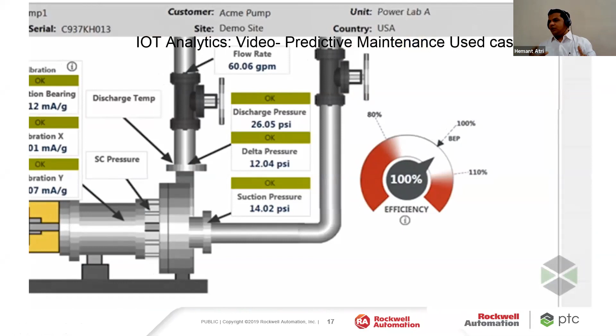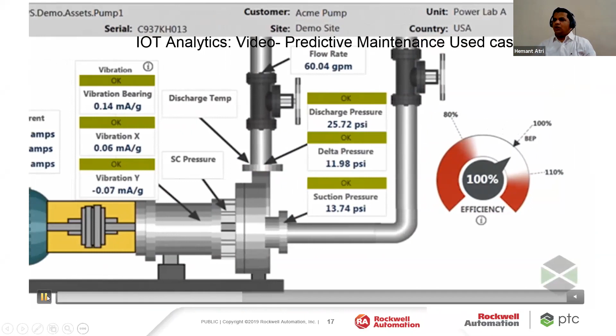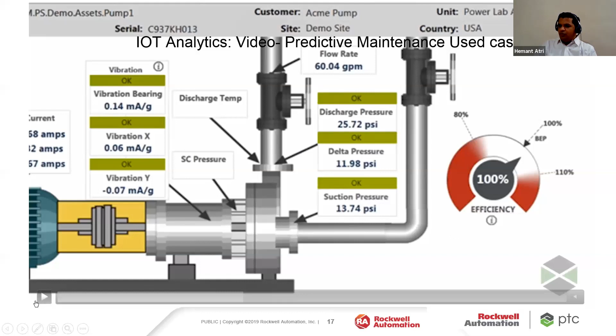This is what we call the pump's normal operating condition. Here you can see the critical parameters for a pump to function normally: the vibration levels, the discharge pressure, the discharge temperature, and the efficiency. These inputs we have modeled based on the flow rates and the current amperes, or the load taken by the motor of the pump. You can see the model is showing at what efficiency the pump is running right now.